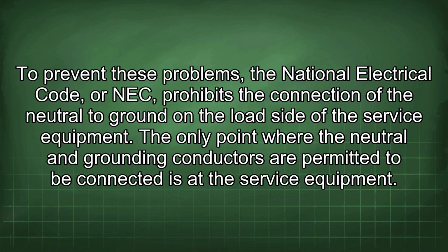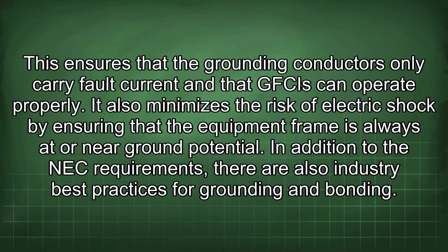To prevent these problems, the National Electrical Code, or NEC, prohibits the connection of the neutral to ground on the load side of the service equipment. The only point where the neutral and grounding conductors are permitted to be connected is at the service equipment. This ensures that the grounding conductors only carry fault current and that GFCIs can operate properly. It also minimizes the risk of electric shock by ensuring that the equipment frame is always at or near ground potential.